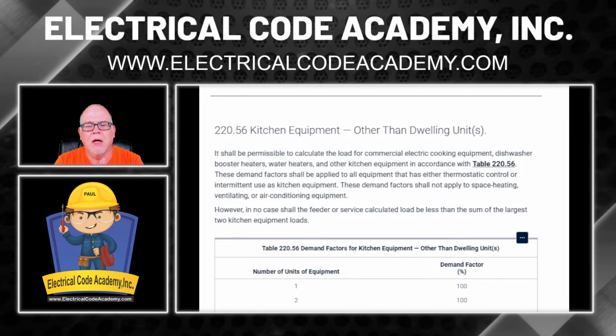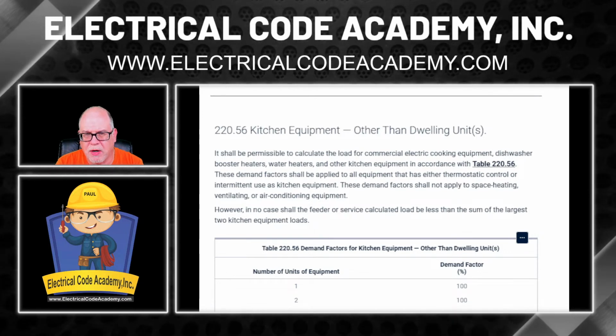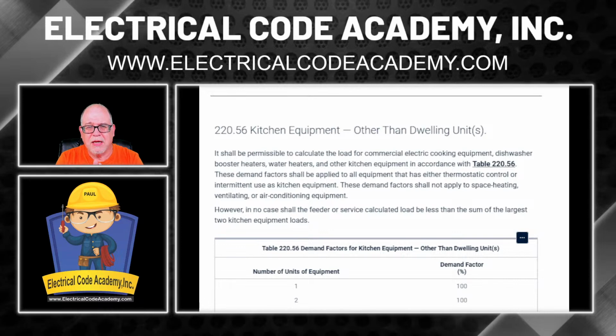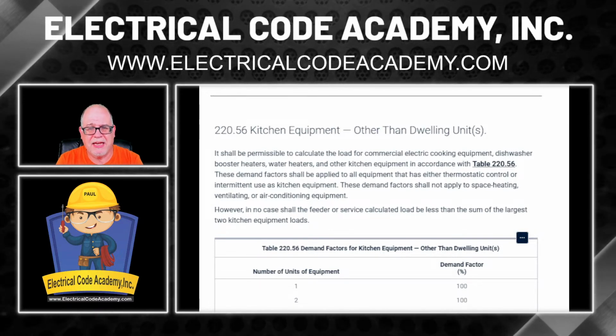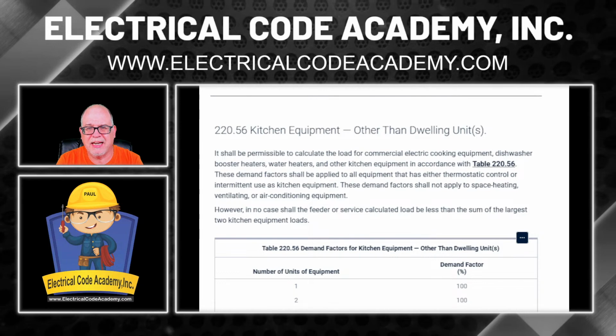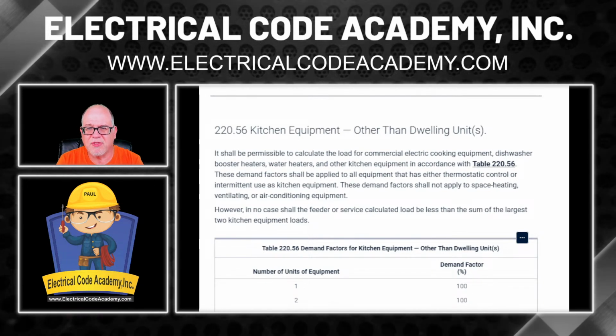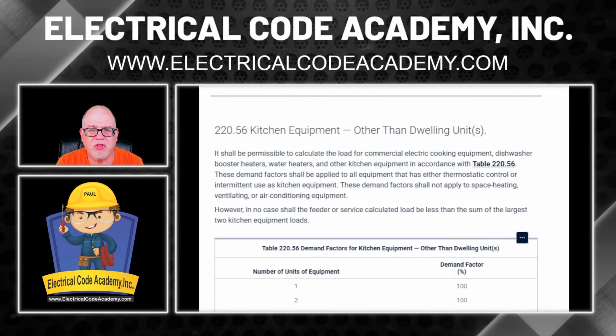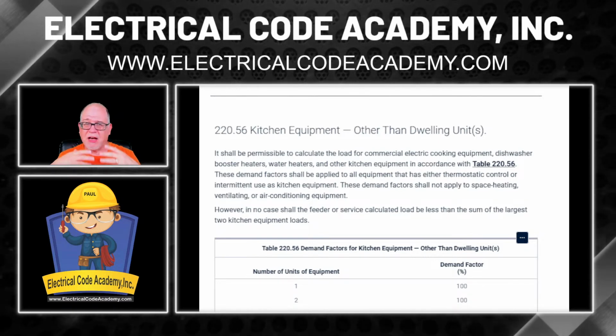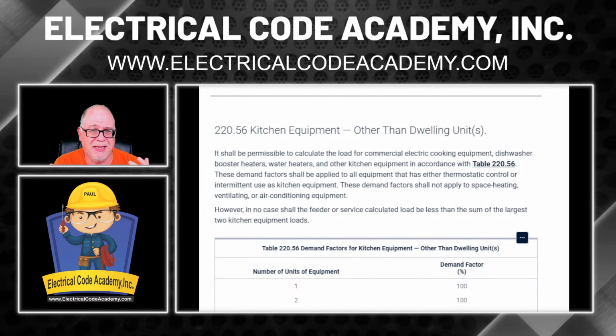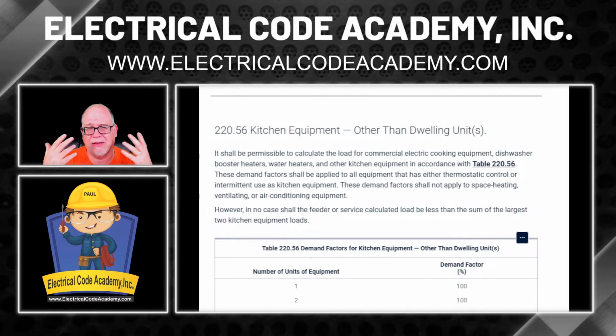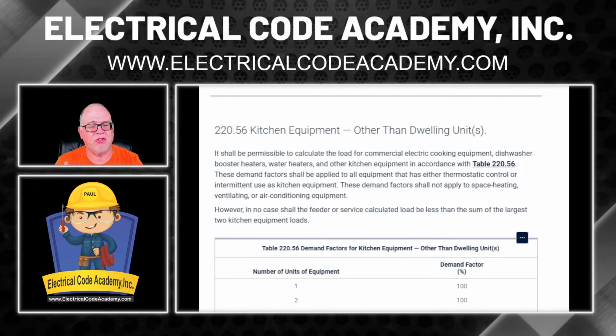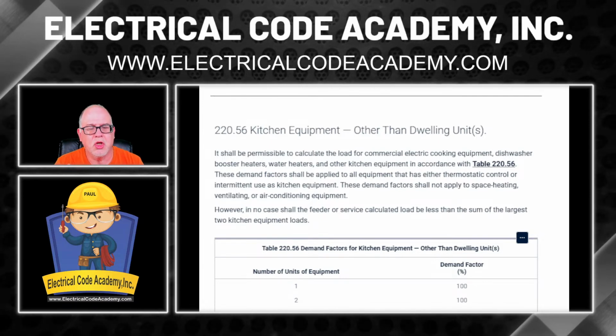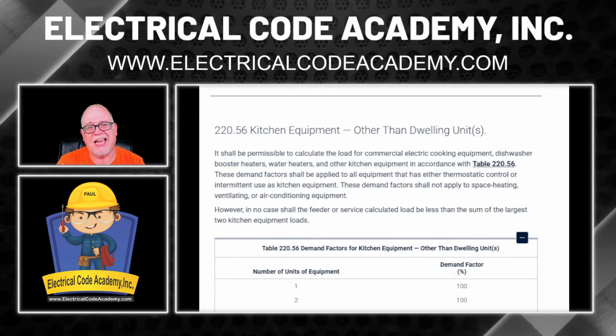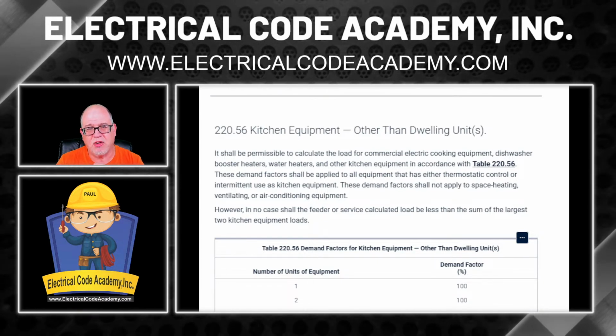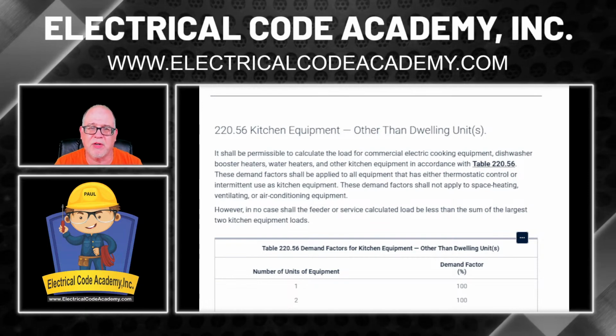Okay. One of the most important aspects I want you to be aware of is where it says, however. It says, however, in no case shall the feeder or service calculated load be less than the sum of the largest two kitchen equipment loads. Now, in the full calculation, it's probably never going to be, because we haven't even taken the other loads in the building into consideration. But in this question, you also have to understand that the math we're getting ready to do can't be less than the two largest pieces of equipment.